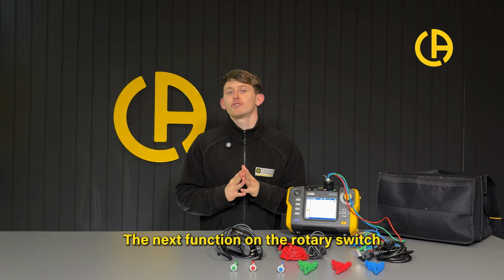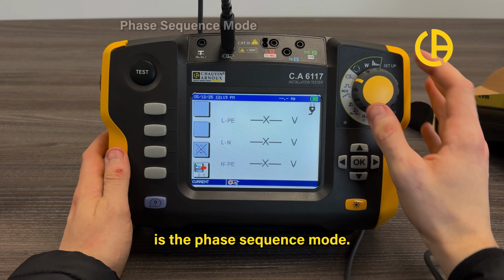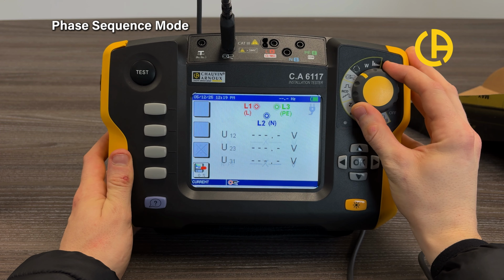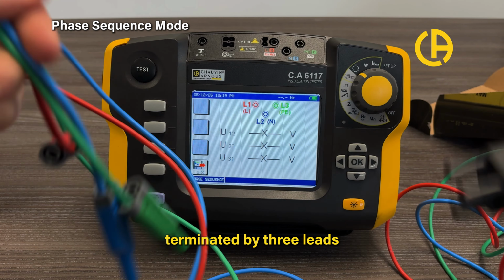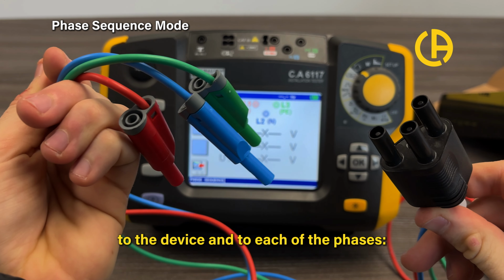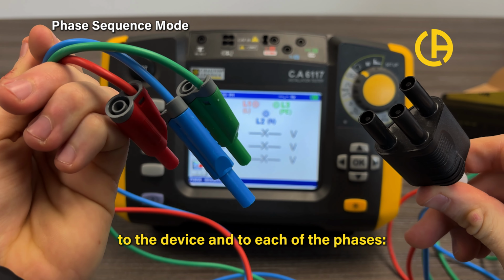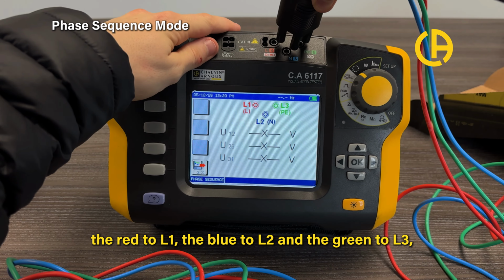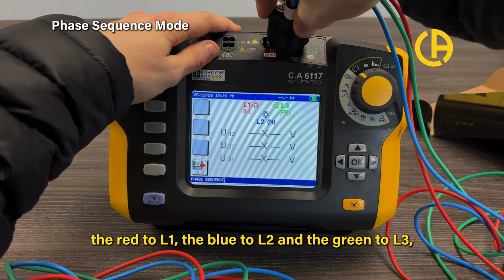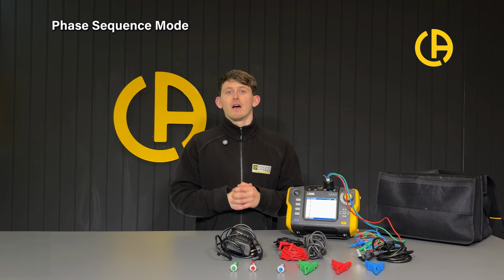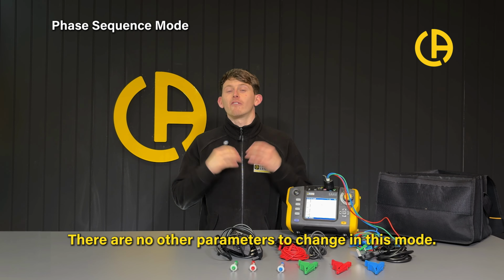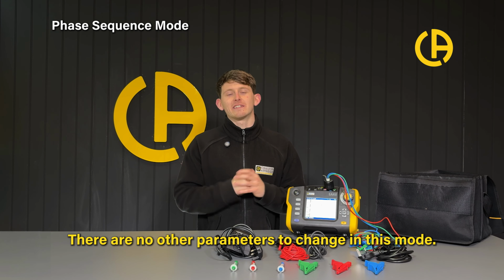The next function on the rotary switch is the phase sequence mode. Connect the tripod measuring lead terminated by 3 leads to the device and to each of the phases, the red to L1, the blue to L2 and the green to L3. Then press test. There are no other parameters to change in this mode.